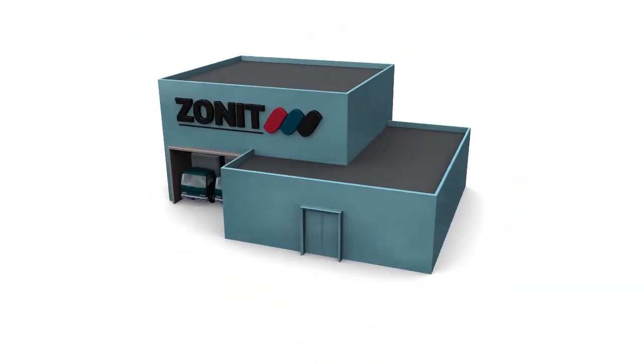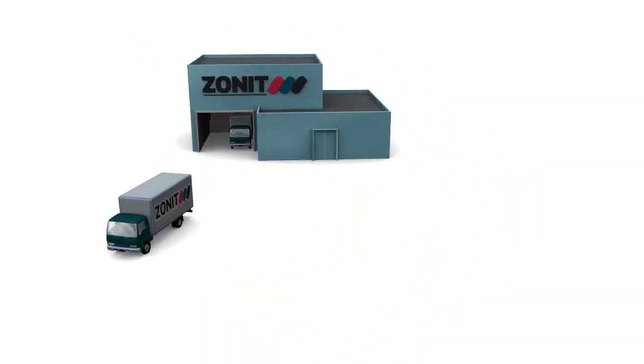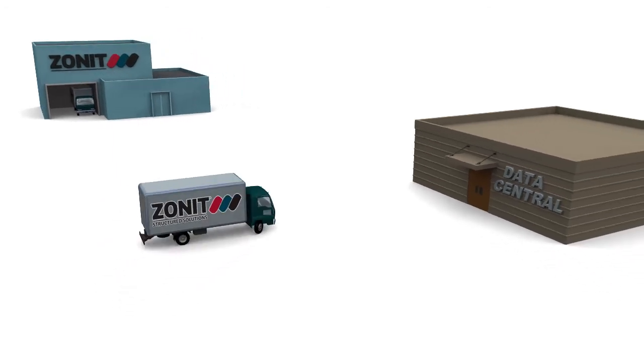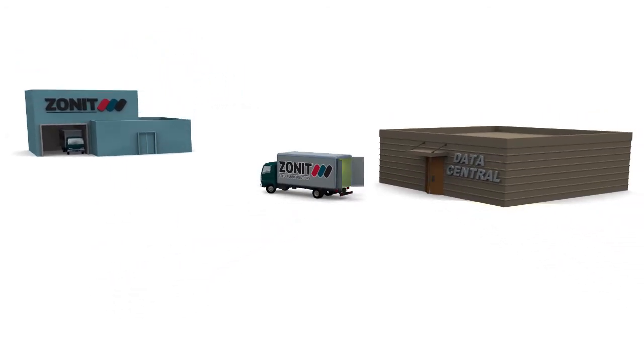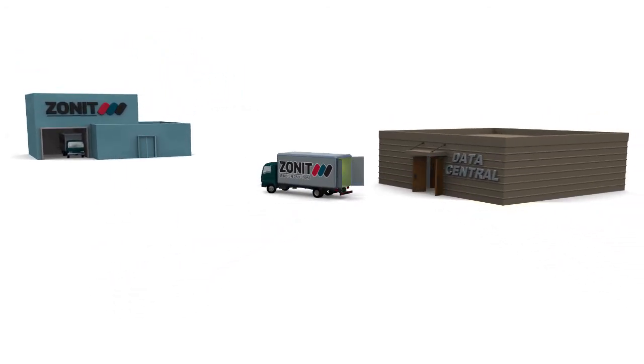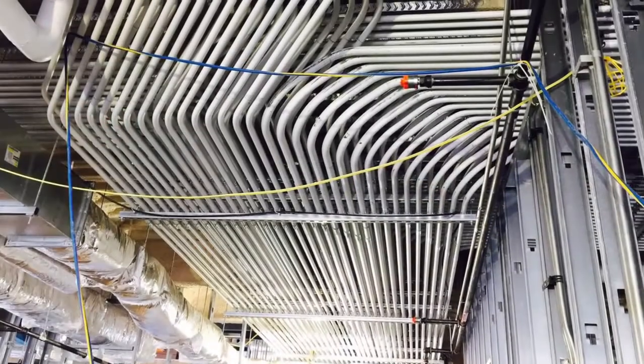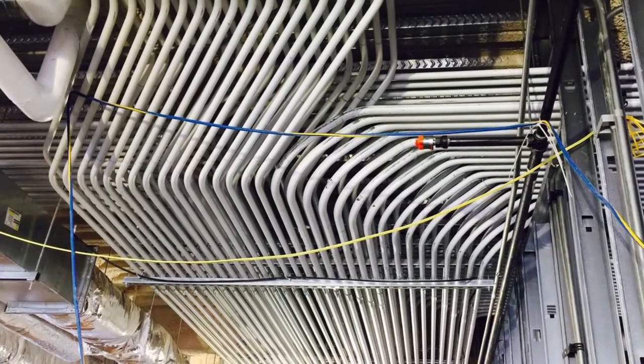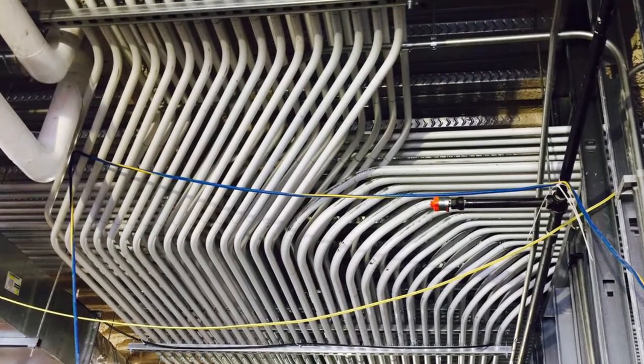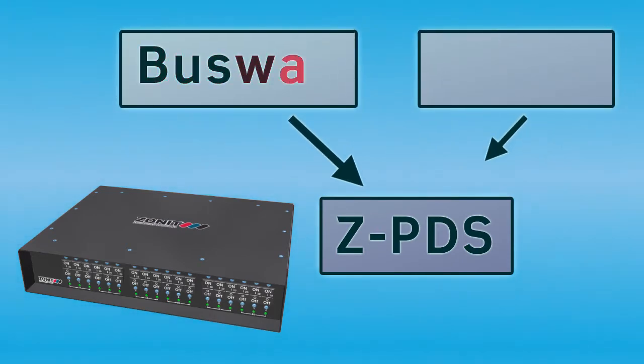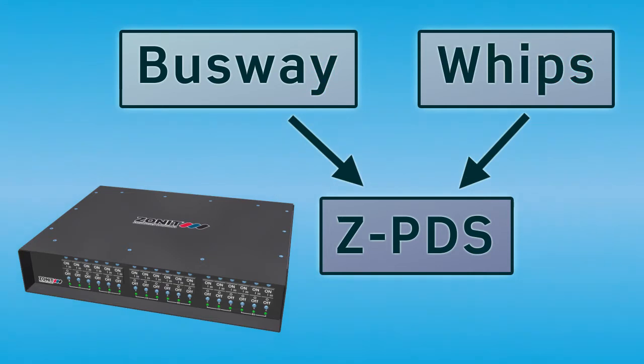Sixth, all or most of the elements of a Z-PDS deployment can be built off-site and just installed on-site, which is much less expensive than the standard methodologies where some or all of the power system elements are custom-built and installed on-site. To summarize, install the Z-PDS at the rack system fed from either option number 1 or option number 2. Make all needed changes at the rack from that point forward.